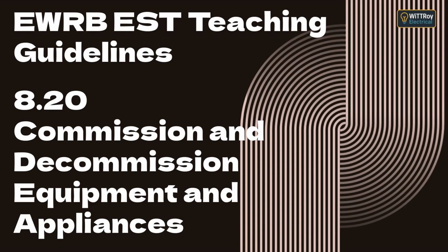So remember this summary. Active and neutral reversed, dangerous switch position. Neutral and earth reversed, live frame. Active and earth reversed, deadly touch voltage. Always double-check connections before turning power back on.